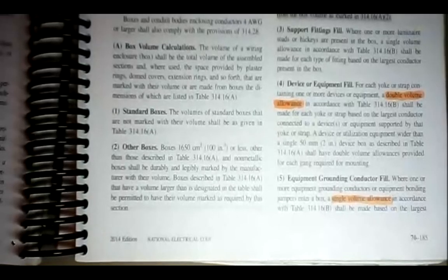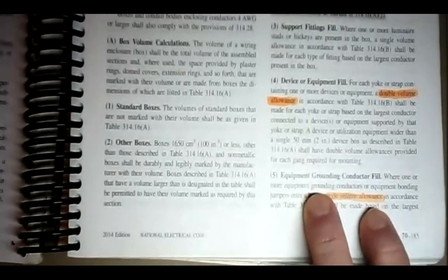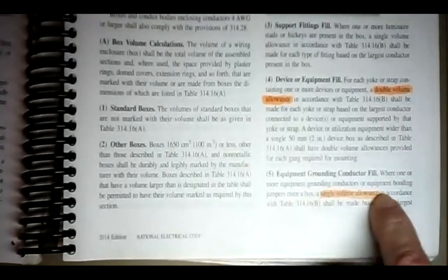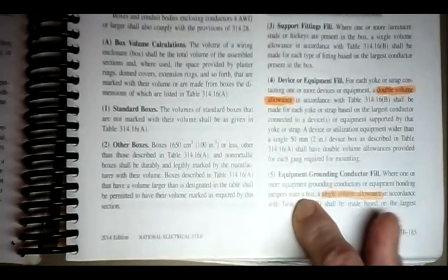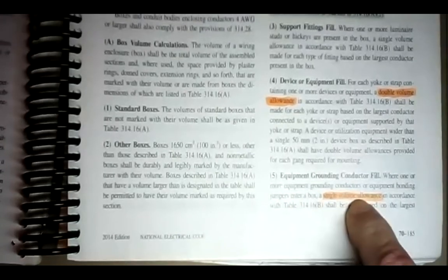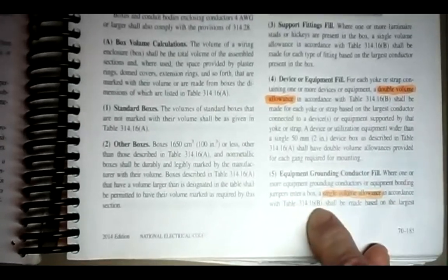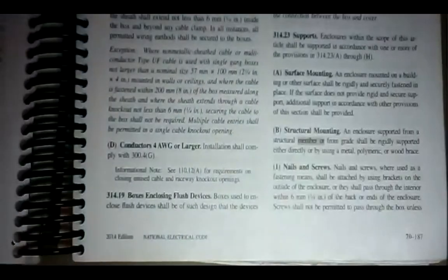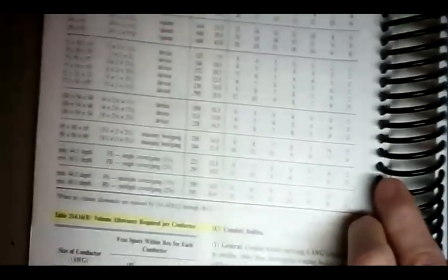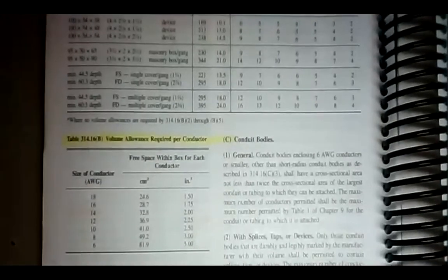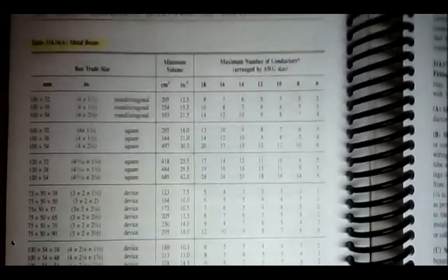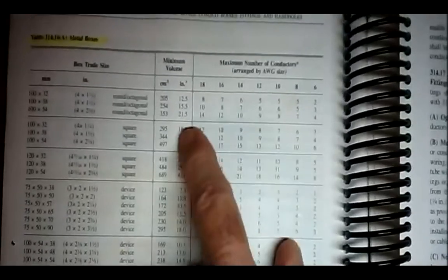For equipment ground fill: where one or more equipment grounding conductors or equipment bonding jumpers enter a box, a single volume allowance per table 314.16B shall be made based on the largest conductor in the ground group. So it's one deduction total for equipment grounding conductors, regardless of how many there are.